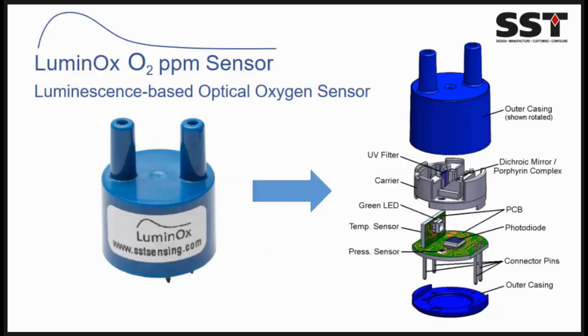So here's the proposed ppm sensor which I have in my hand. This is not the size. This is for demonstration purposes. In fact, this is the size. So SST actually have an oxygen sensor on the market. So this sensor goes from 0 to 25% oxygen. So basically, the principle is the same, but what we have done is we have changed out a few of the materials or the components within the sensor and the oxygen sensing layer itself, which is what I focus primarily on. So here you can see a breakdown of the sensor.